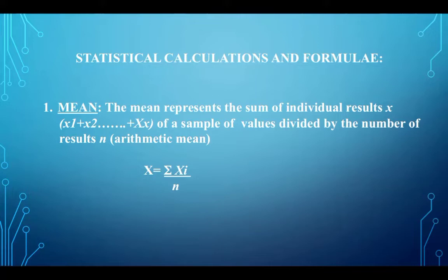We follow it for another 20 data points and then reassess our lab mean. Am I right, sir? You will use the previous standard deviation, based on the CV, to calculate the standard deviation for the present one. If the acceptable CV is 4%, then calculate the standard deviation based on that.